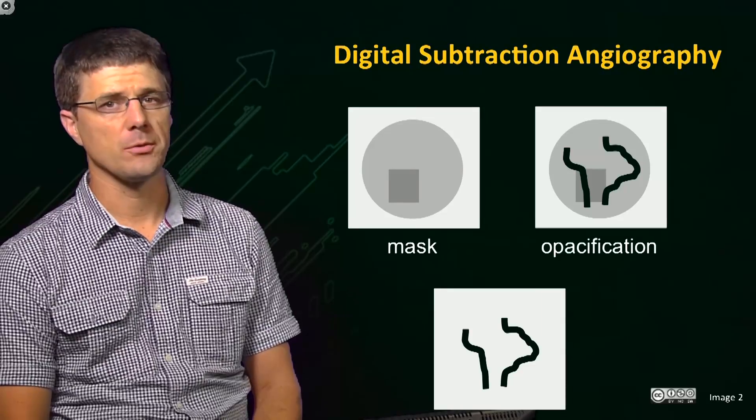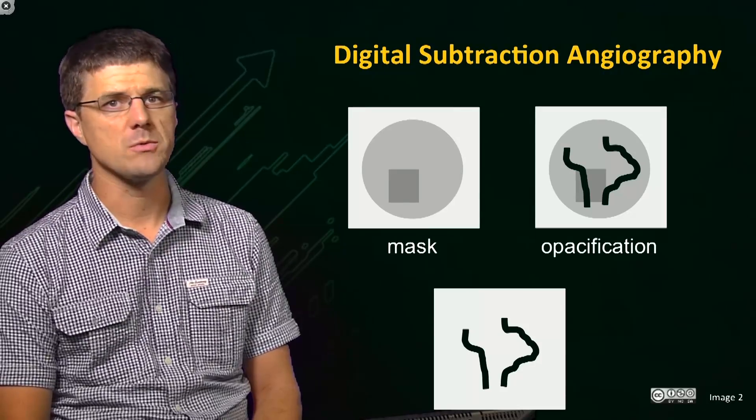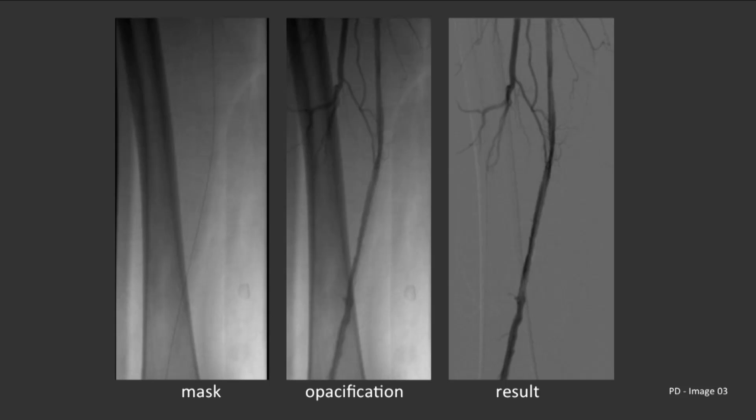Only parts of the image that are different between the two acquisitions are shown in the final output image. In this example, the final image will only retain the two black structures that appeared in the opacification image. The typical process is first to acquire a normal image, also called a mask image, that we can see on the left. This image is stored in memory and then a second image is acquired once contrast has been injected. This second image is often called the opacification image. These two images can then be linearly subtracted from each other on a pixel per pixel basis to create an output image.